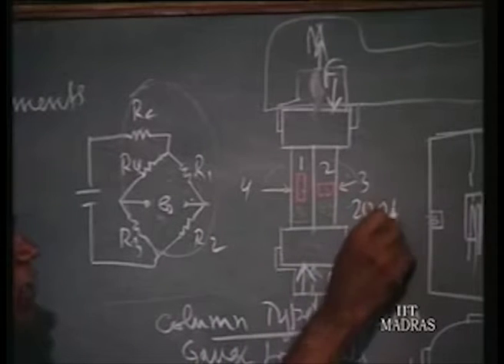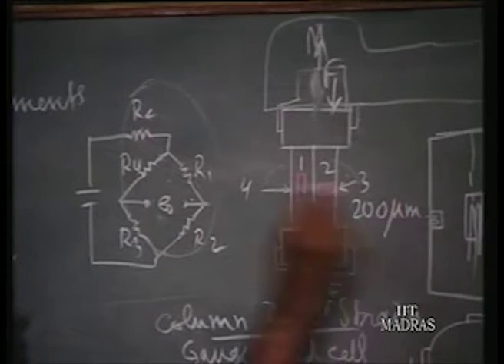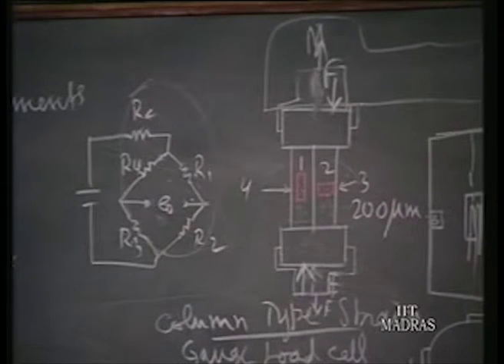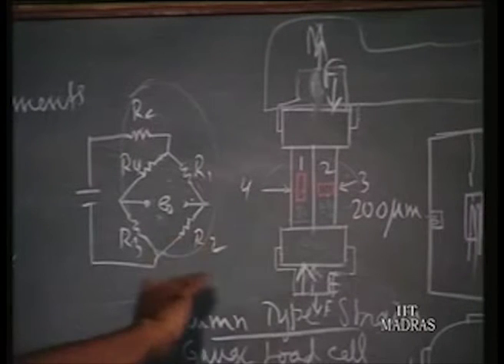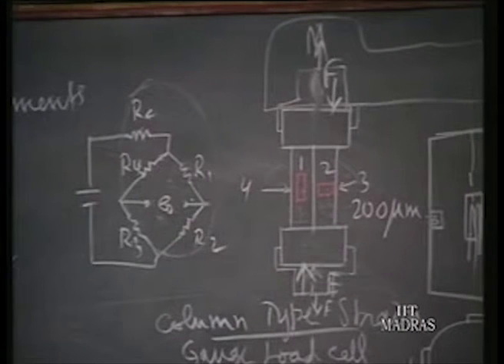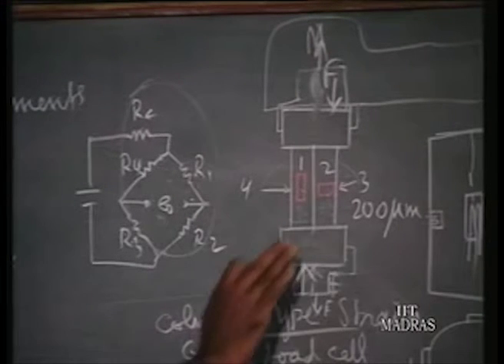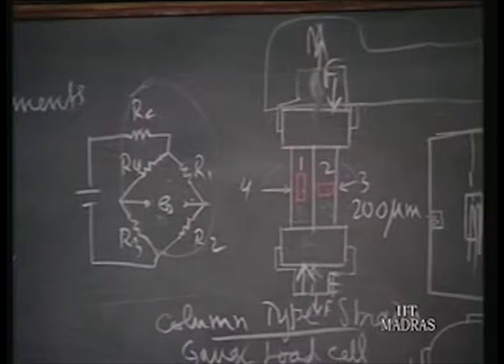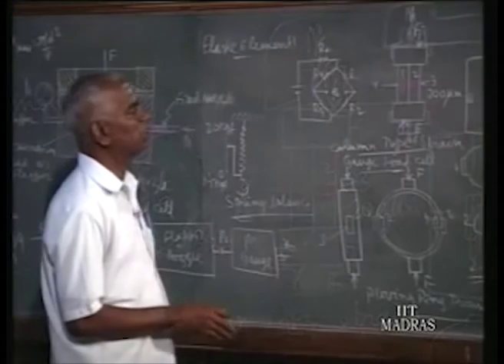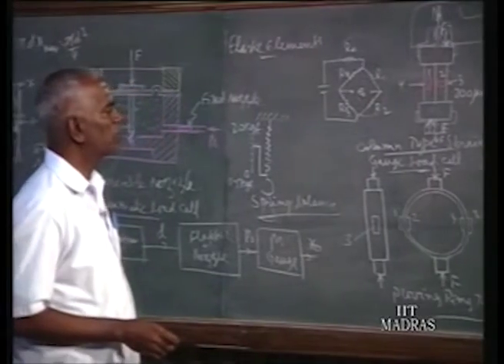So it will produce at least 200 micro strain. That is what we expect. At least 200 micro strain should be there for the maximum loading. If it is 0.1 or 0.2 micro strain, then it will not produce any effect. So for this load cell, where we want to fix the strain gauges, there should be sufficient strain. To that extent, you have to weaken that place and only then fix the strain gauges. This is what is important.